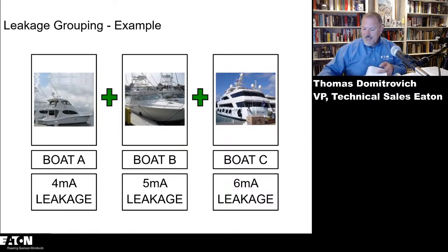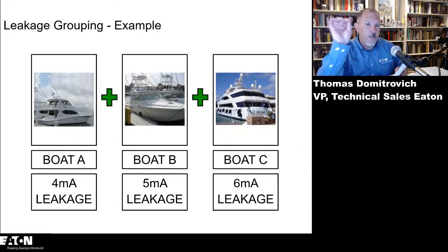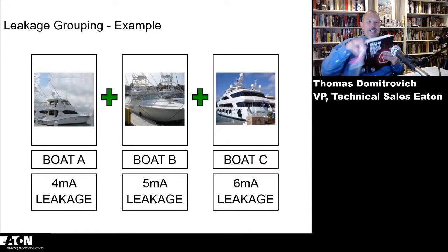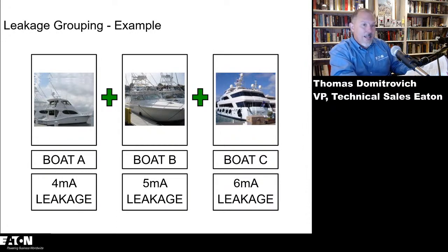But I think it's in 682. You've got to look at this one, Dawn, because I will guarantee nobody is doing this. In 682, there is a requirement around services, I believe, here it is, 682.11, for you naturally and artificially made bodies of water people out there. It says, on land, the service equipment for floating structures and submersible electrical equipment shall be located no closer than 5 foot horizontally from the shoreline and live parts shall be elevated to a minimum of 12 inches above the electrical datum plane.